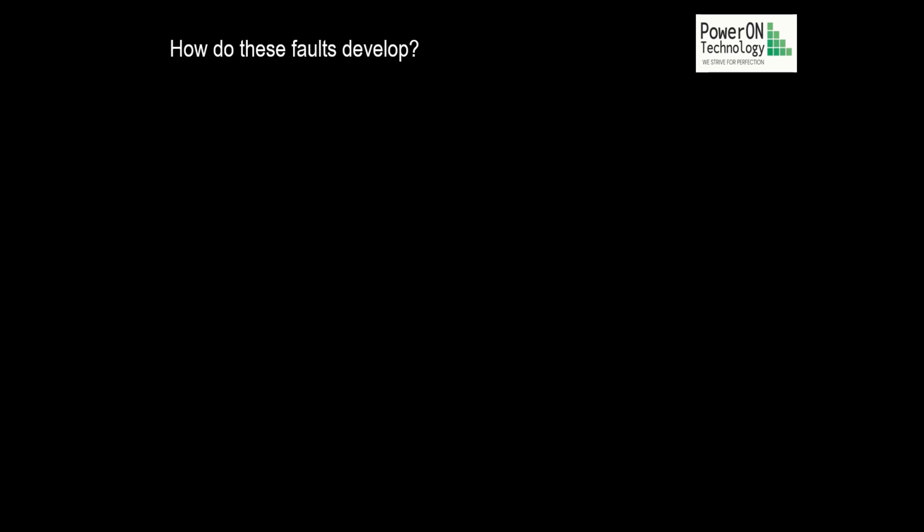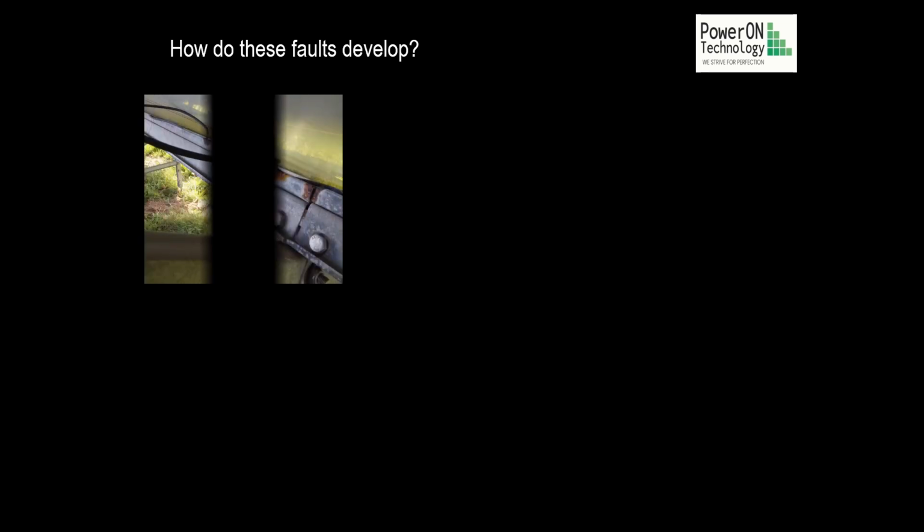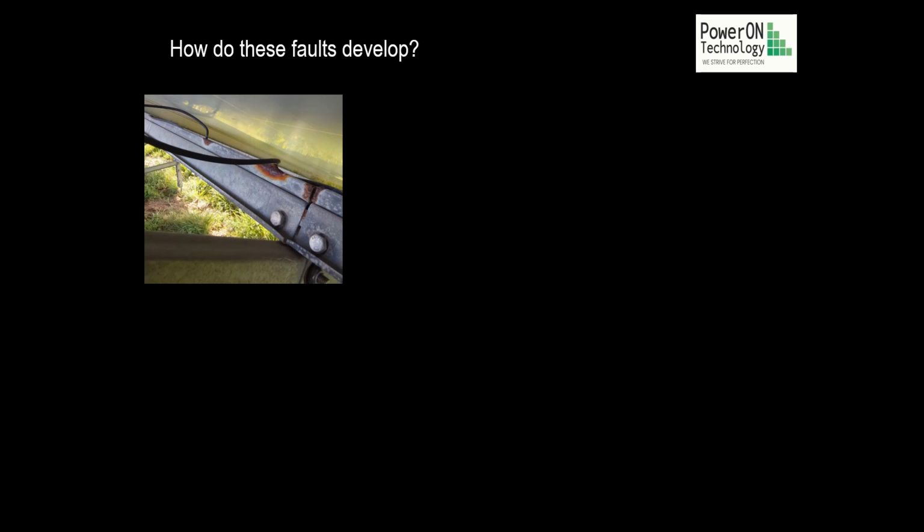So far, we considered the effect of the faults, but where do they come from? The first obvious cause of these faults could be mechanical damage or incorrect installation. But there is a second long-term fault that is much more prevalent. Because a PV system is a DC system, it is prone to electrically induced buildup as shown here. Simply put, the conductors eventually weld themselves together in this way and cause a short.